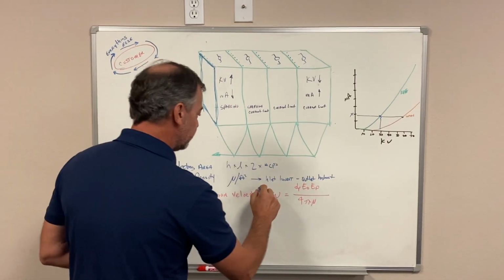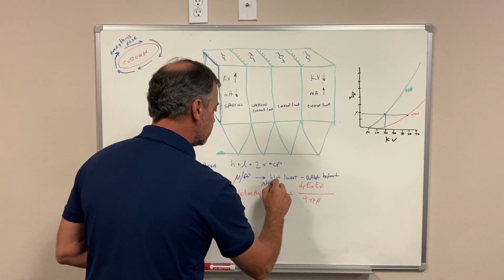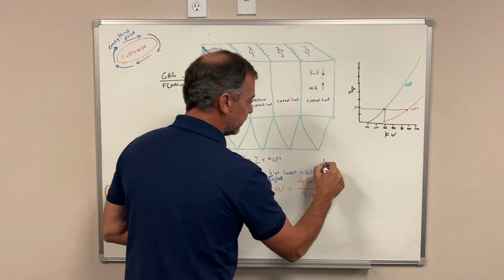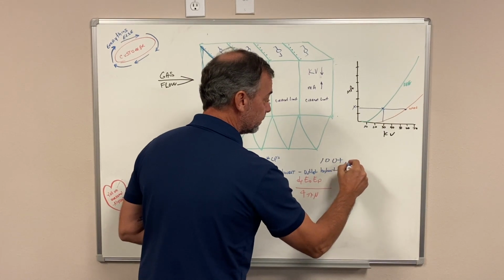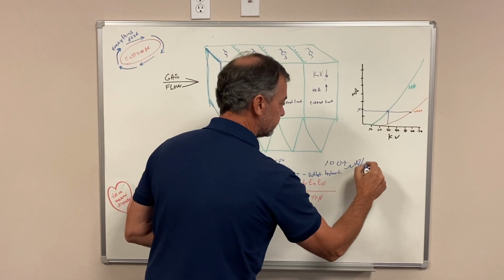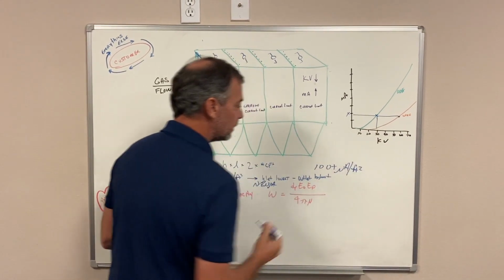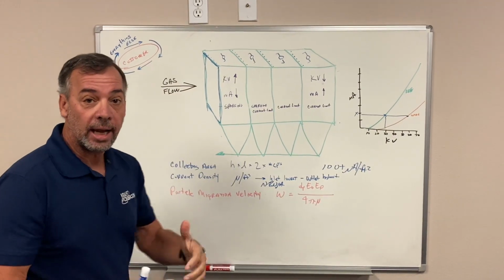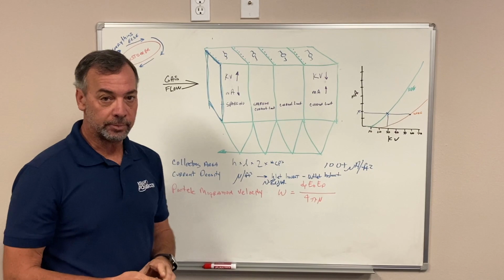So, and these are rule of thumbs based on your type of discharge electrode has a lot to do with it. But your inlet fields may be 10 to 20 microamps per square foot. Sorry for my bad writing. Your outlet field could be as high as 100 plus microamps per square foot. So one of the things when you're assessing is, do I have enough ampacity for this field?